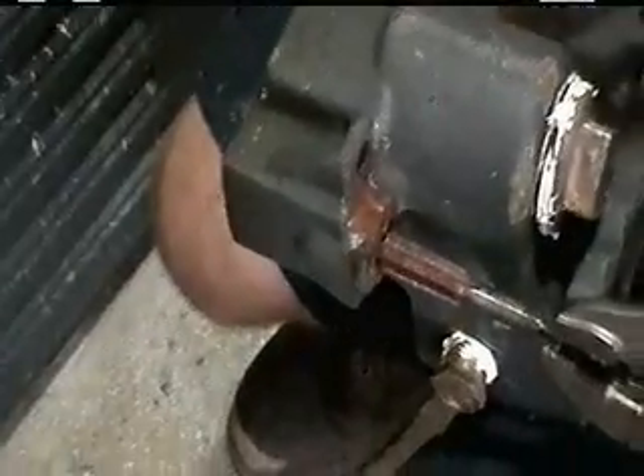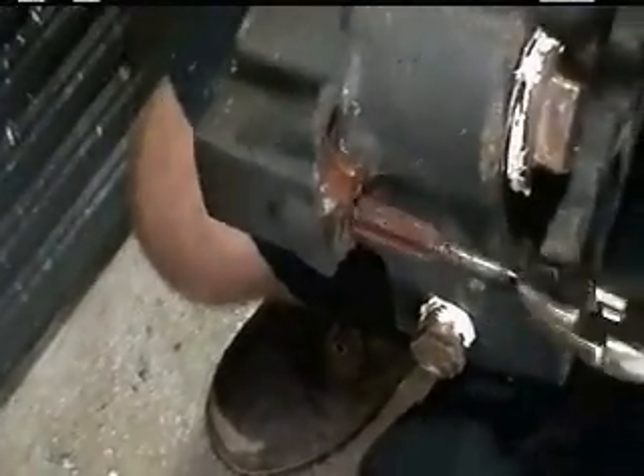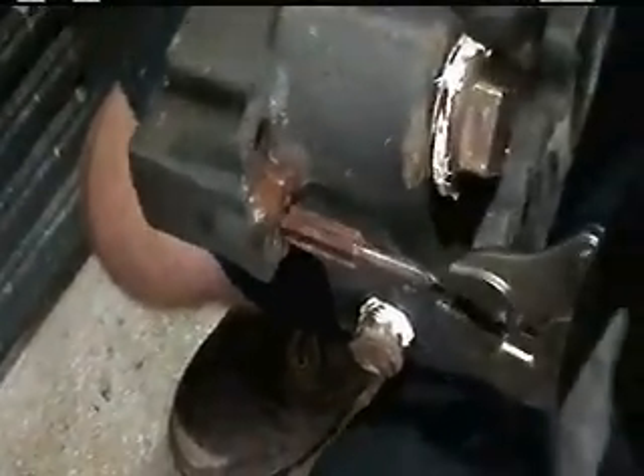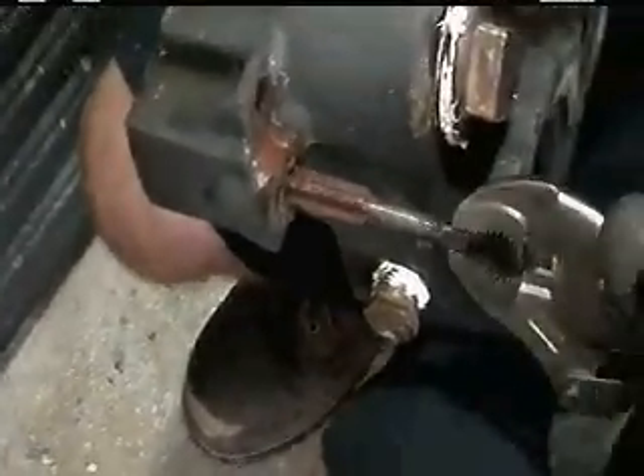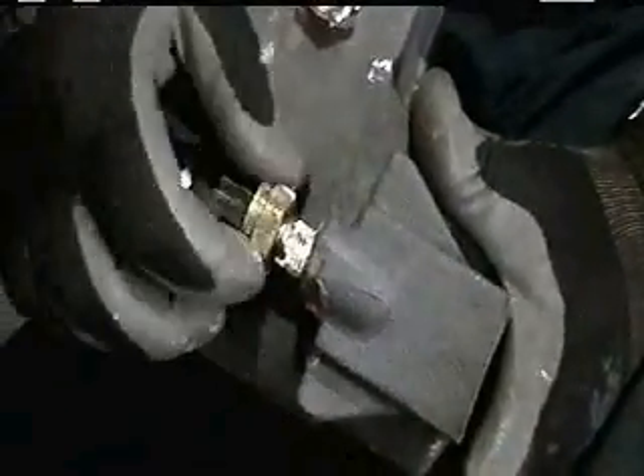You can see how hard that can be at some point in time. This whole process that you're seeing here in a matter of minutes usually takes about a half a day to do all this work. So here he is cleaning the tubes, continuing to clean the tubes, but he's also replacing the rubber gaskets. We're putting on a new high temperature safety switch. It's what we call a high limit switch. It senses if the water gets too hot and it shuts down the heater. It's called a high limit safety switch.